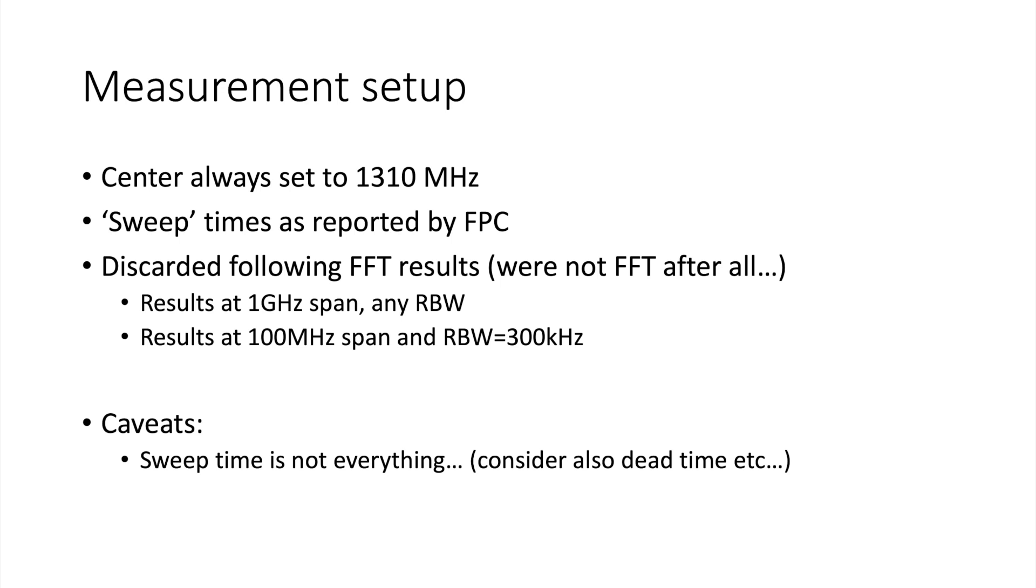One important caveat I want to mention here is that sweep time is not everything. A device could also have a certain dead time between the measurements that could be relevant or not to you. This is actually something that I think the CMU 200, which I'm going to talk about a little bit later, differs from the device I'm looking at today. So sweep time is not the only thing that you want to consider to be able to catch fast transient type of signals.